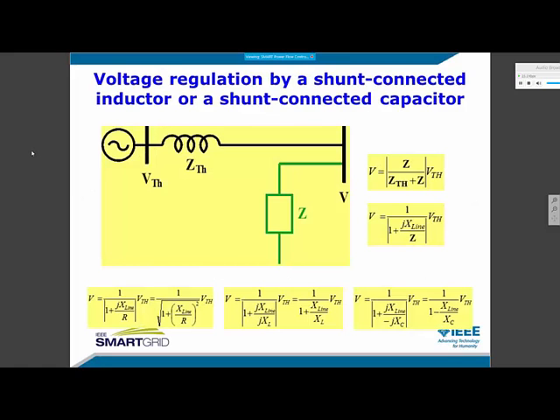Now let's examine the speed of response feature in voltage regulation applications. The principle of operation of a voltage regulator is explained in this voltage divider circuit, where the entire power system is represented by a voltage source and a Thevenin impedance. Considering the line is reactive, it can be easily shown that the shunt-connected capacitor is the one that increases the voltage at the point of common coupling, and the shunt-connected inductor is the one that decreases the voltage at the point of common coupling.